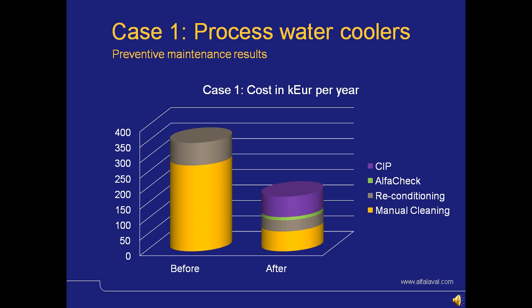Before the optimization of the maintenance procedure, the customer was looking at a yearly spendings of around 330,000 euro. Remember, this involves a portion of the gaskets being changed every 4 years. After the optimization, instead of changing gaskets every 4 years, we're now changing them every 8 years, which means there's half as much cost in that. The manual cleaning went down significantly to about a fifth of what it was before, and those are the savings made. Of course, there is an added cost of the CIP and also AlfaCheck, but looking at the total cost, you can see that the cost has decreased from around 330,000 euros down to about 170,000 euros a year.